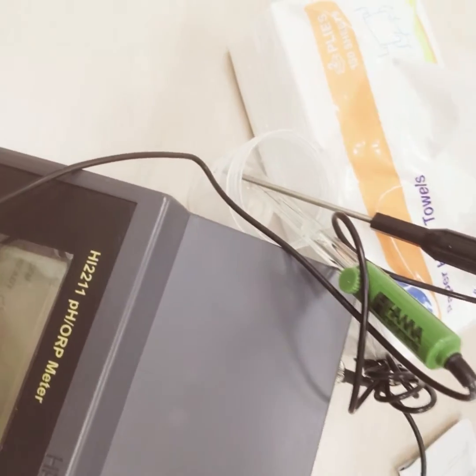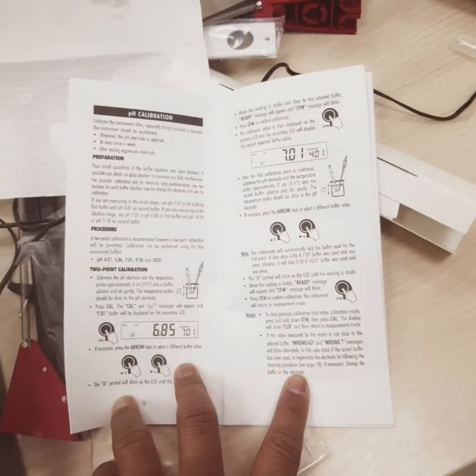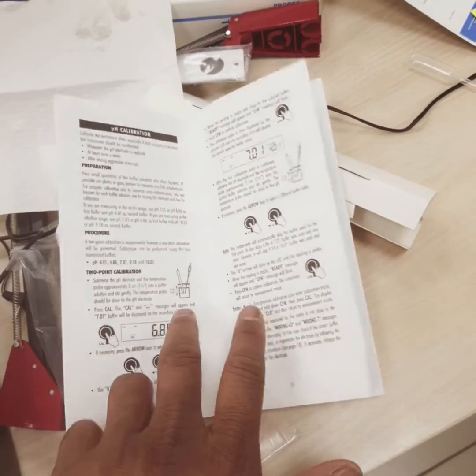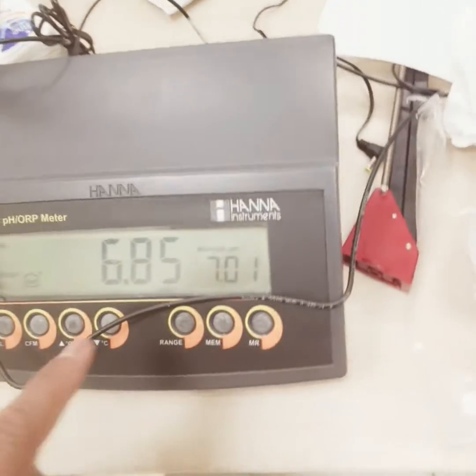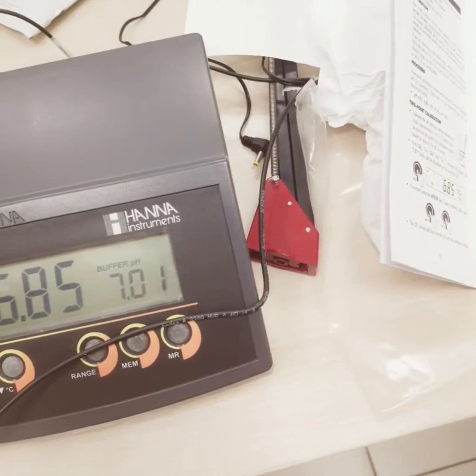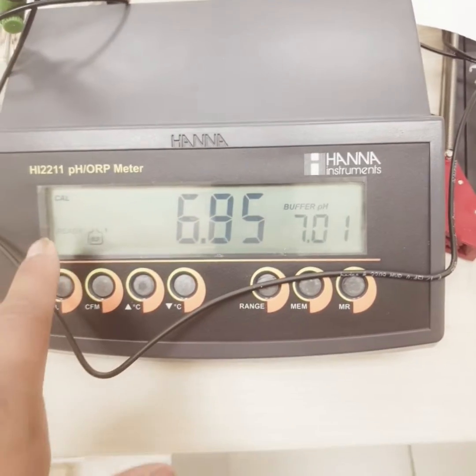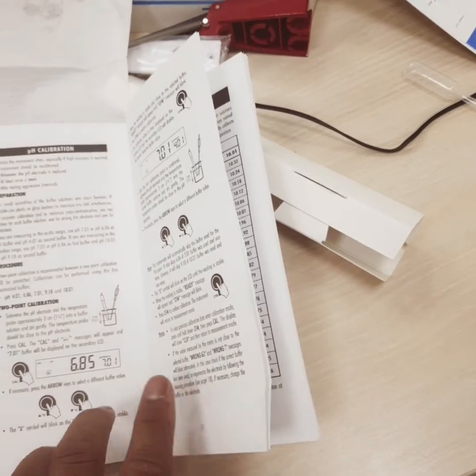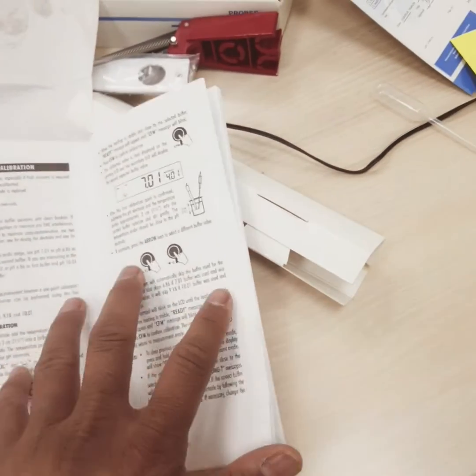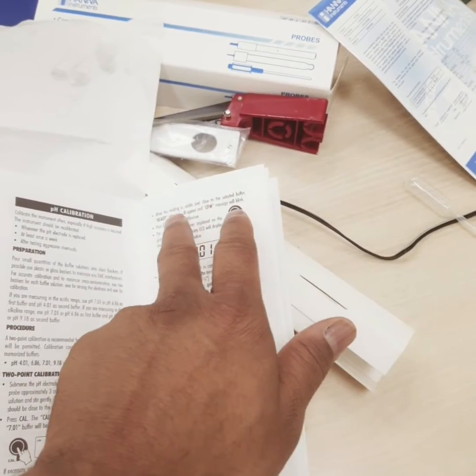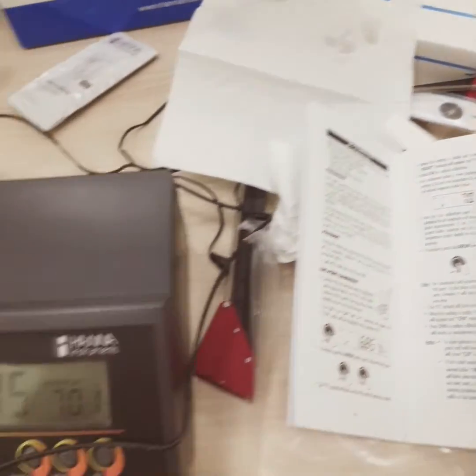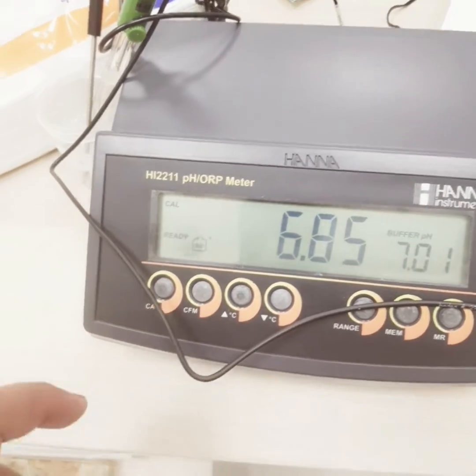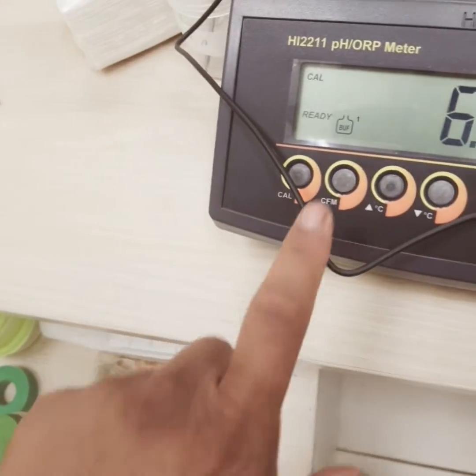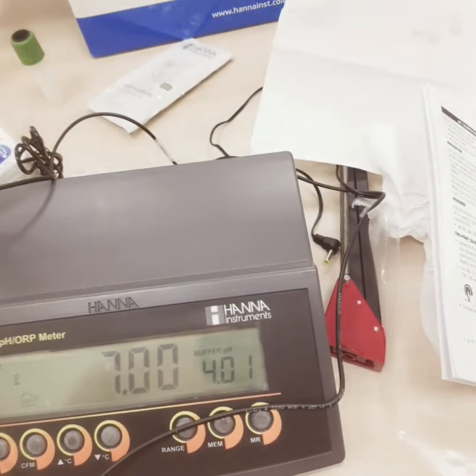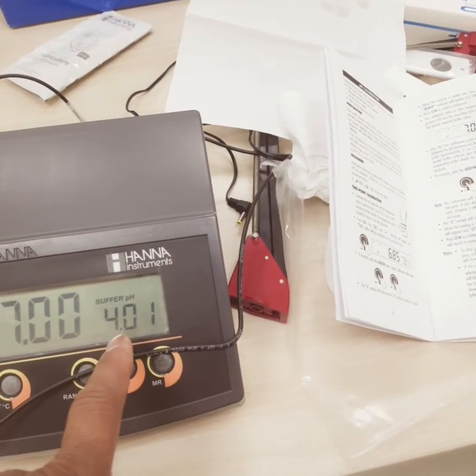Okay, here, so you can see here, submerge the pH electrode, press cal, and then a message will appear. So you can see here. Okay, so it shows, if necessary press the arrow key to select a different value. We don't need to do that. And when the reading is stable close to the selected value, the CFM message will blink. So it's like a blinking CFM message. So the value is close. Press CFM to confirm. So we'll say okay. Now we have to add buffer 4.